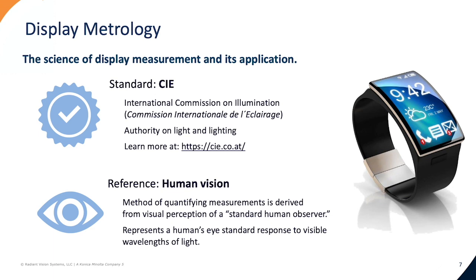The reference is human vision. The CIE's methods of quantifying measurements is derived from studies of the visual response of a standard human observer. We calculate the perceived output of a display based on the standard human eye response to visible wavelengths of light.